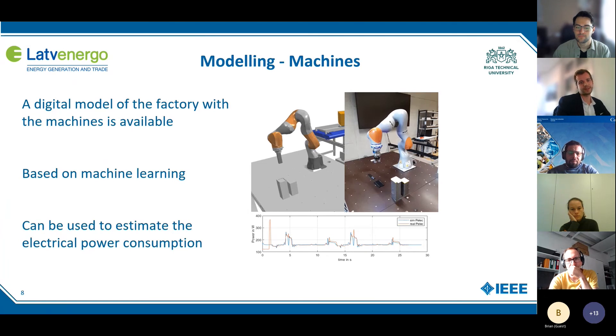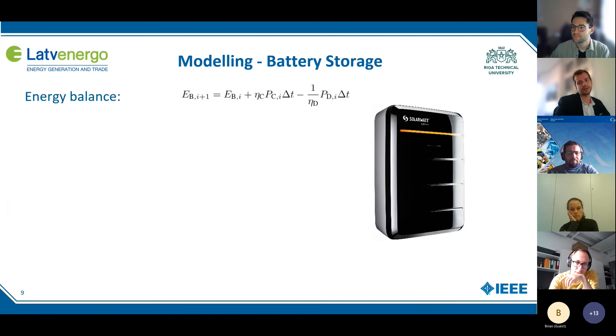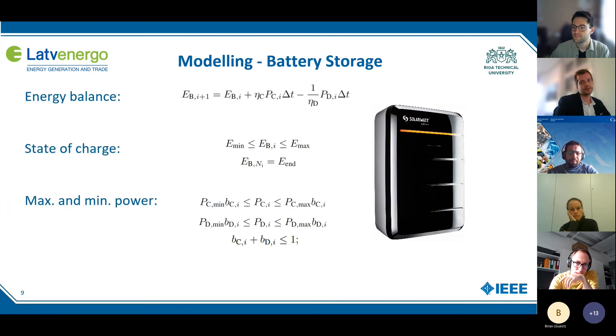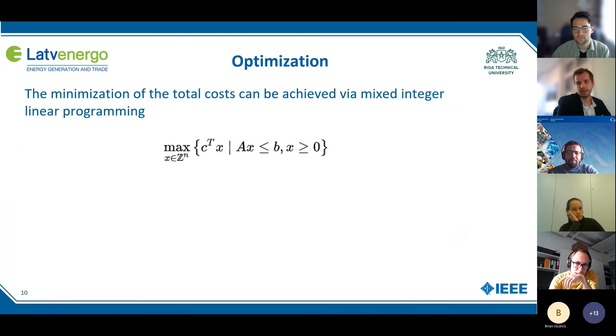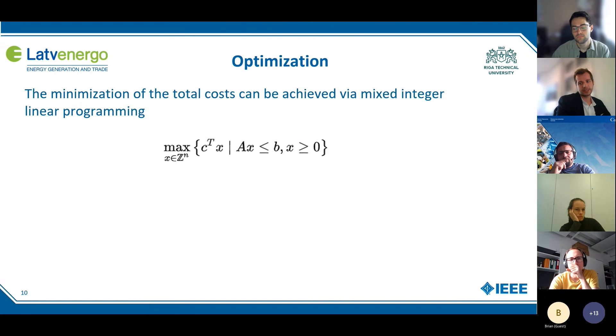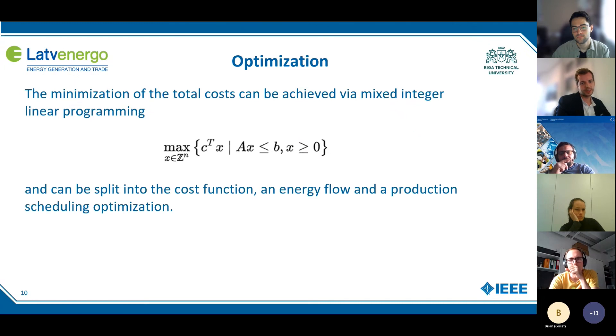This is then used as the digital twin. Next we can see the model of the battery storage. For the battery storage, we can just write the energy balances. Using the digital twin model and the energy balances, we can then optimize the system. For the optimization, we are using mixed-integer linear programming. This has the benefit that it's fast and finds the global minima. The optimization problem can be split into the cost function, an energy flow optimization, and a production scheduling optimization.